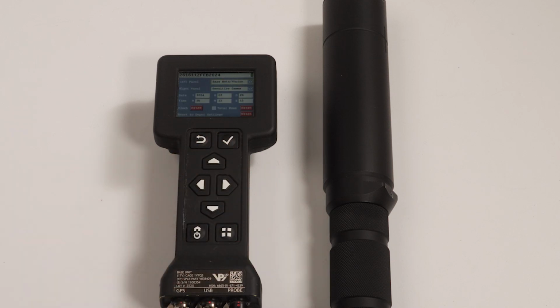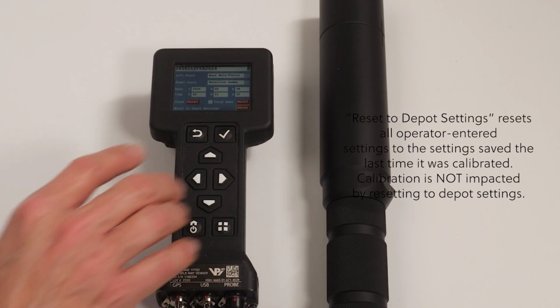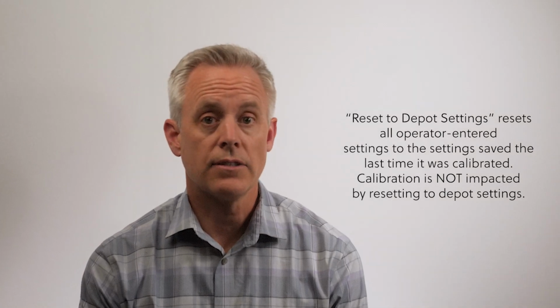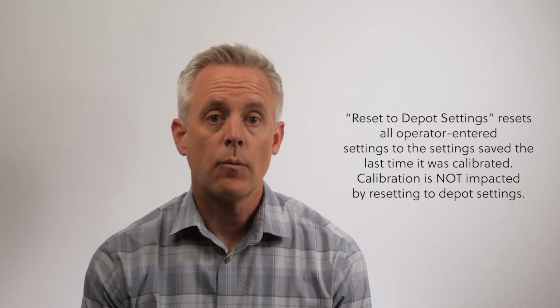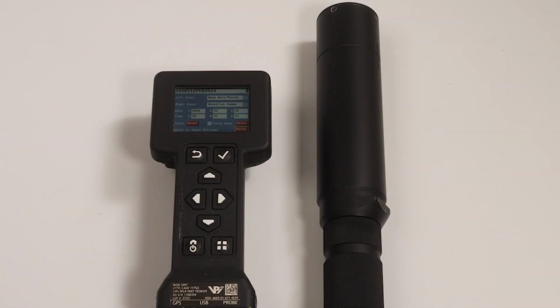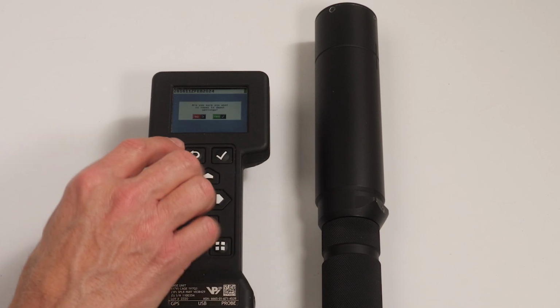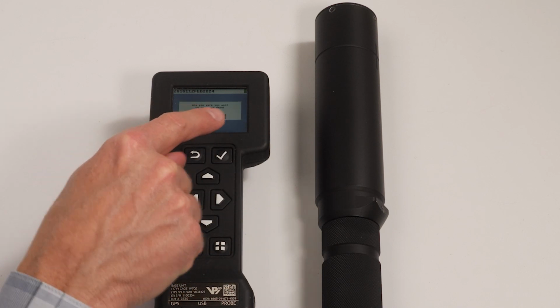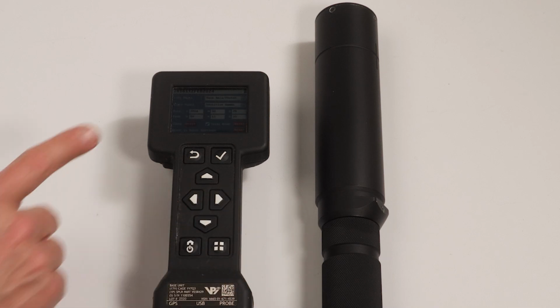Reset to depot settings resets all operator entered settings to the settings saved the last time it was calibrated. Calibration is not impacted by resetting to depot settings. All data logs and the system log are preserved during a depot settings reset. Resetting to depot settings can be used as a troubleshooting step and to quickly change any operator entered settings to the default depot settings. On this screen, highlight the reset to the right of reset to depot settings and press the enter key. Once prompted with confirmation message, confirm the reset by pressing the enter key for yes or pressing the back key to cancel.